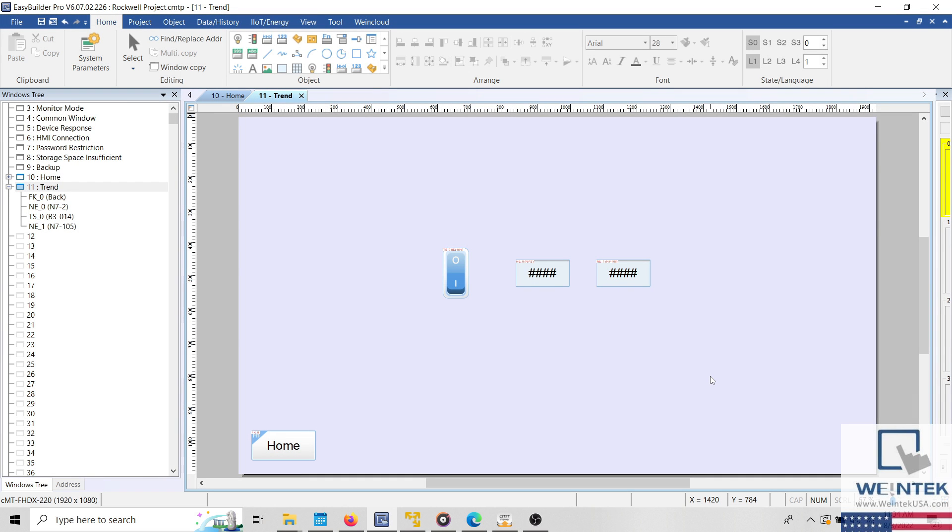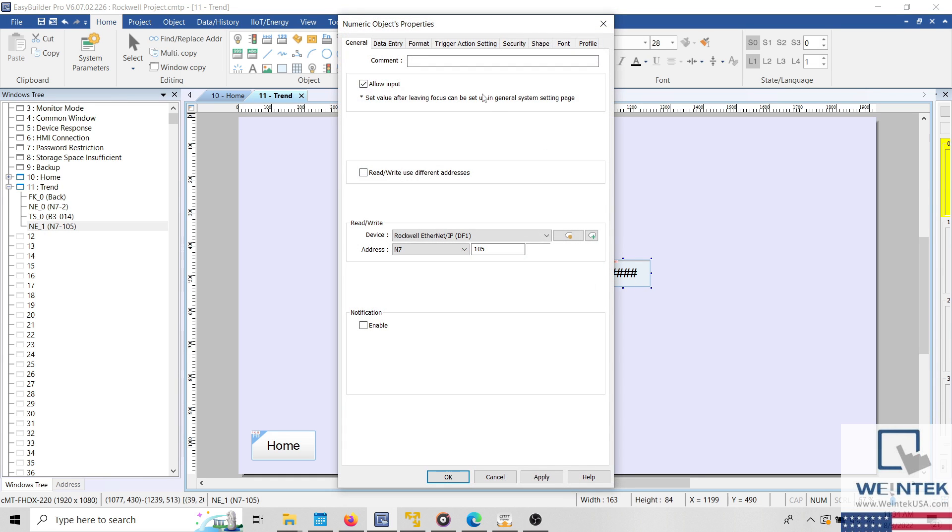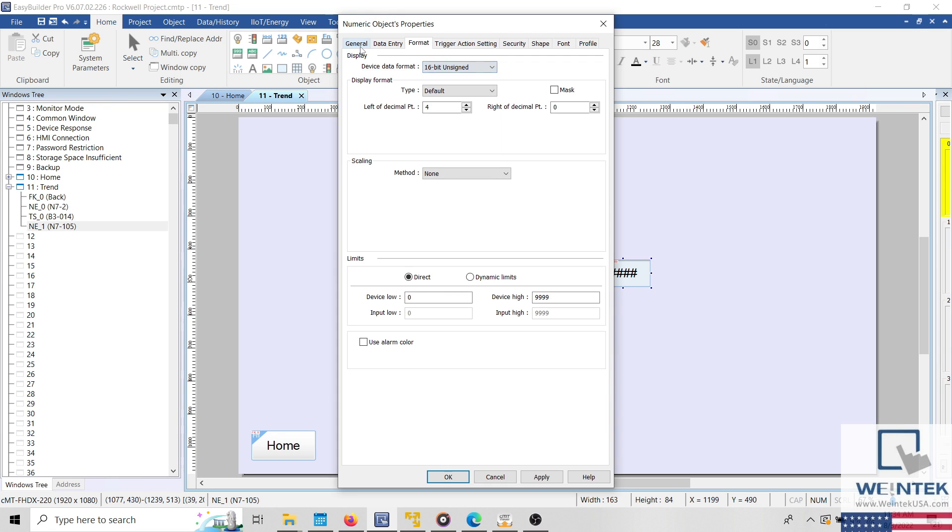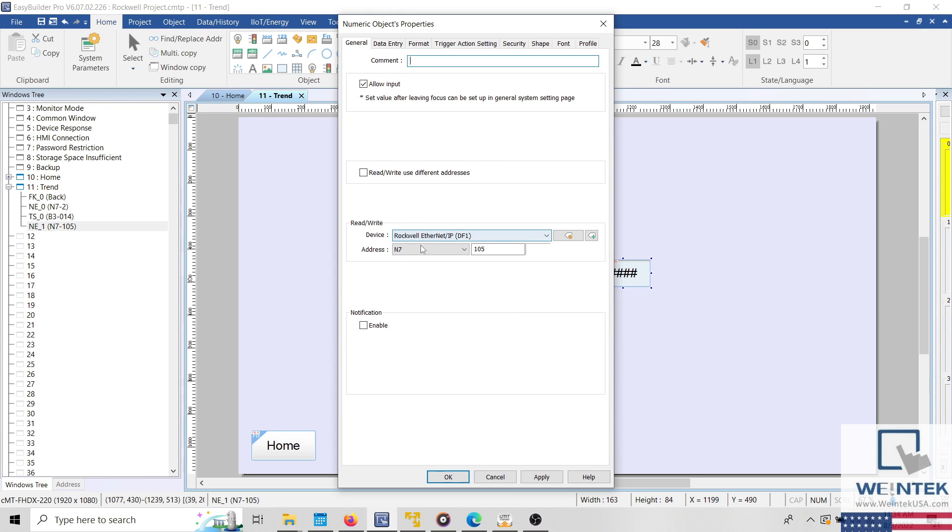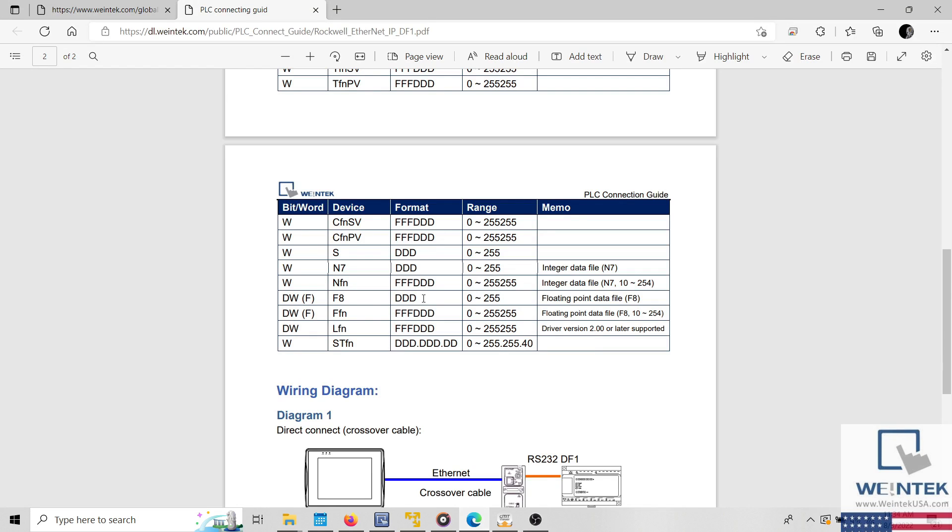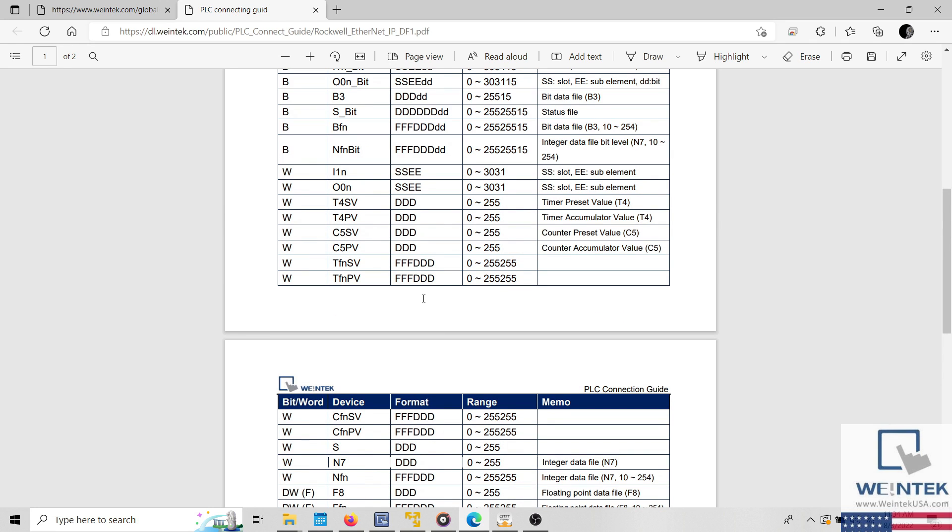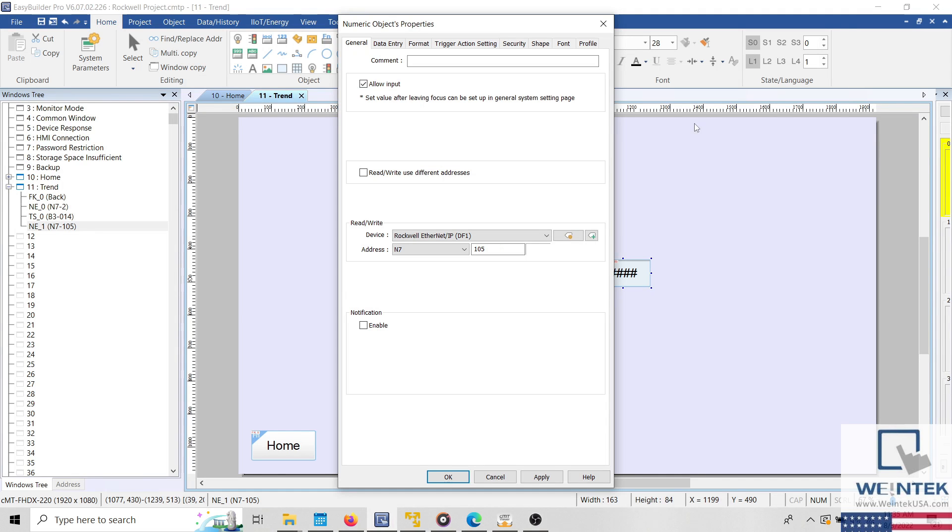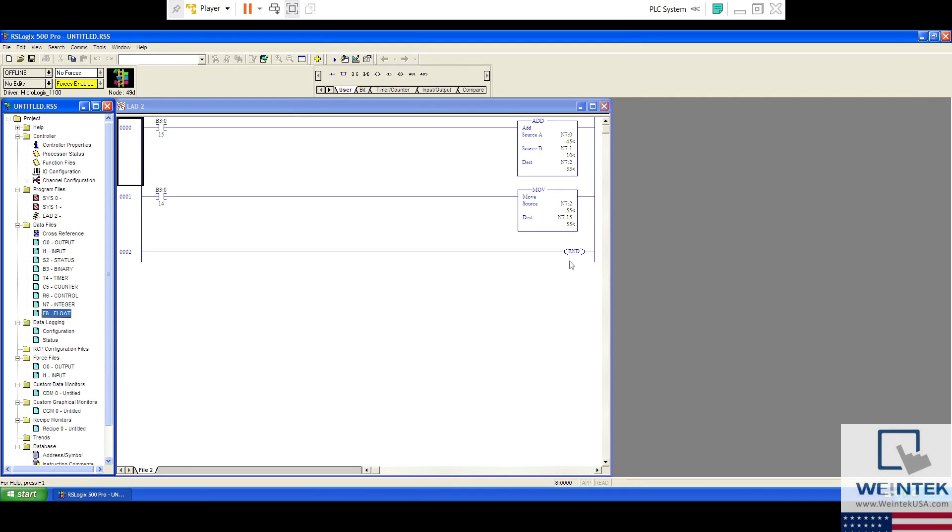There are several reasons why this object may have caused a communication error. An incorrect data type may have been configured within the format tab of the numeric object. The data type should match the data type used by this register within the PLC project. Or you may be using the wrong register type for the device register that you intend to read. Certain drivers have special registers that may correct this issue. Please see the PLC connection guide for the driver used within your application and the user manual for your PLC for more information. The register may not be used or has not been made accessible within PLC memory. Or when using a tag-based PLC, the tag name may have been changed within the PLC project.